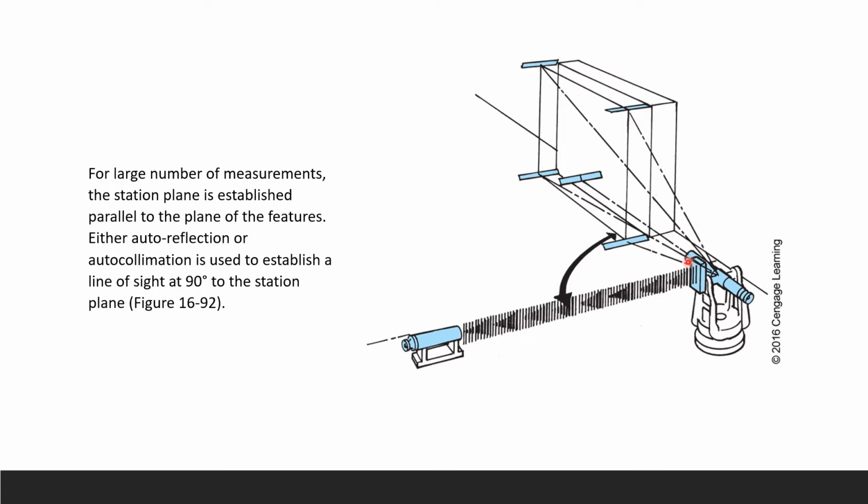The plane is right on this wall, and we're using the JIG Transit with our line of sight right here. That's our reference plane. And then we're going to straighten this vertical line, that's your vertical axis up, by using different prisms, mirrors right there. And then we're going to use the light to get the measurement of this plane.